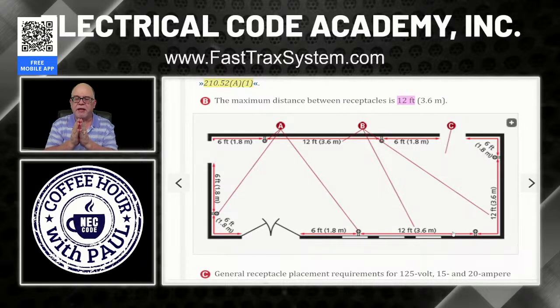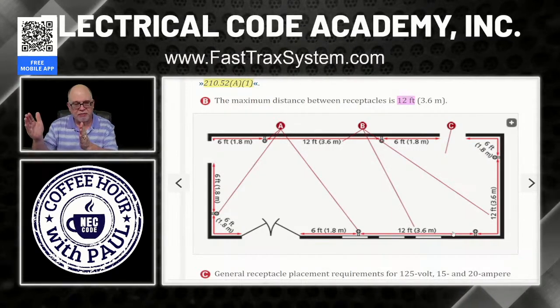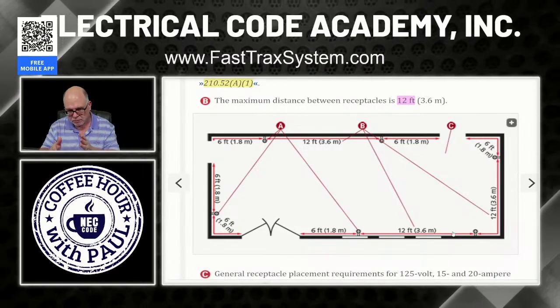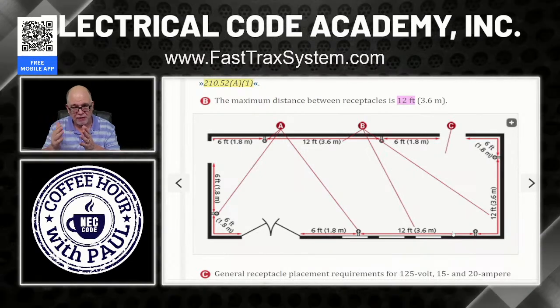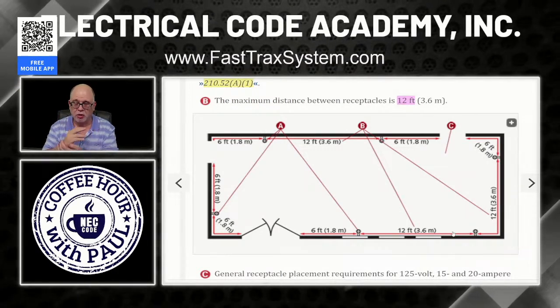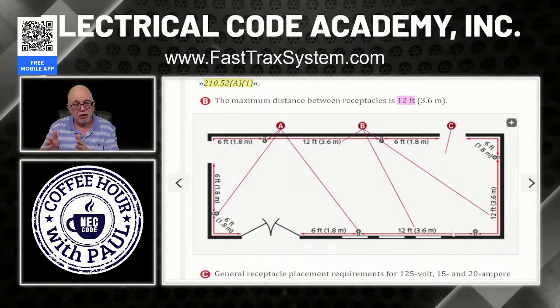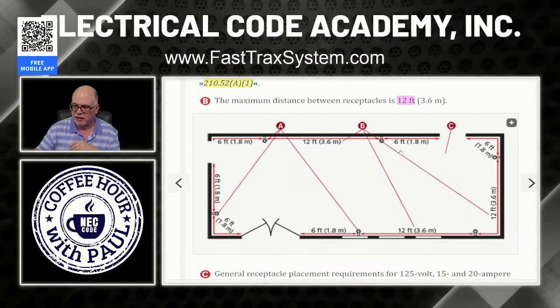and we'll look a little deeper into the code for this. But remember, a break in the floor line, okay, on the wall line, you have to go 6 feet. So let's say a doorway, right? Or a fireplace, or a fixed shelving that's built into the wall, that type of thing. Then that's kind of considered a break in the wall line, okay? Just like if it was an opening, okay? You've got to go read the code because it gives you some scenarios, folks, in that. And so in this case, you're measuring from that break and you have to have a receptacle within 6 feet. So these are pretty evident, right? There's a doorway, doorway, doorway. So that is obviously a break in the wall line. Those make it pretty easy to understand.